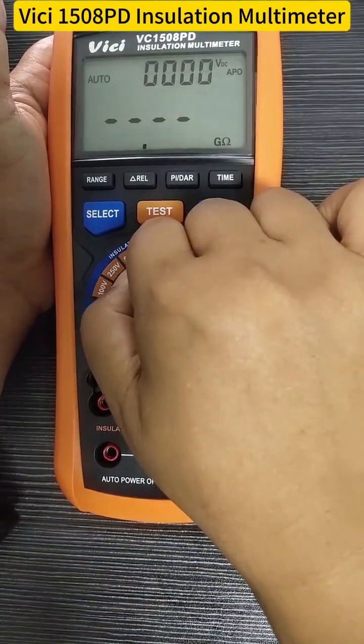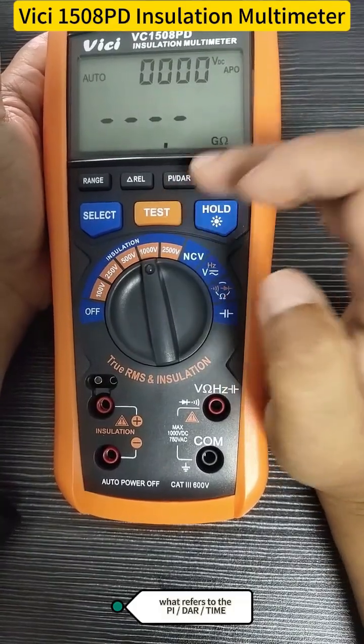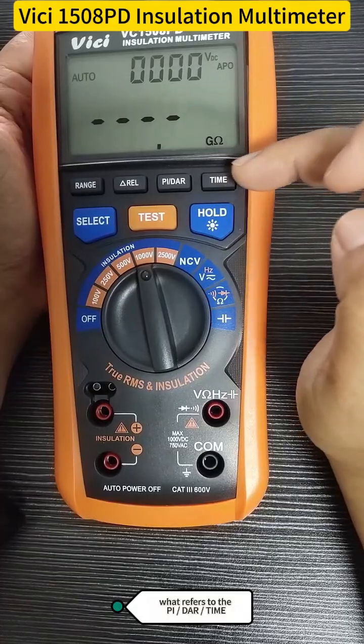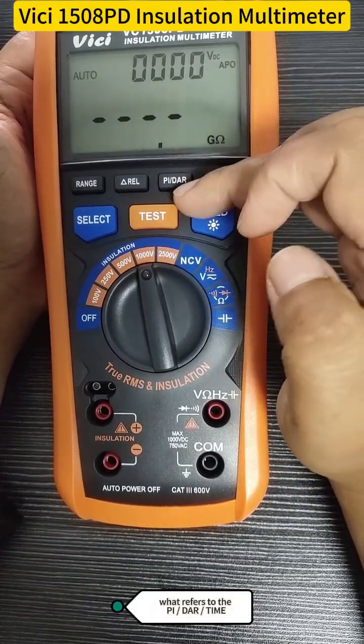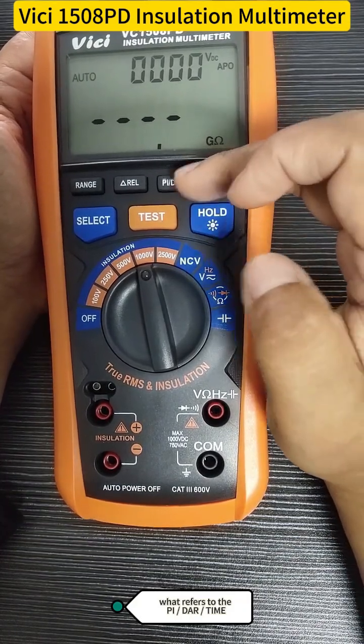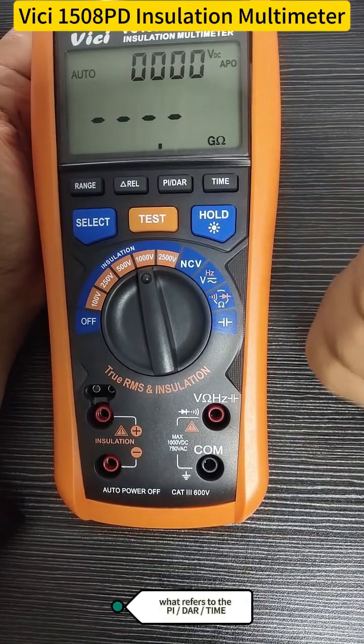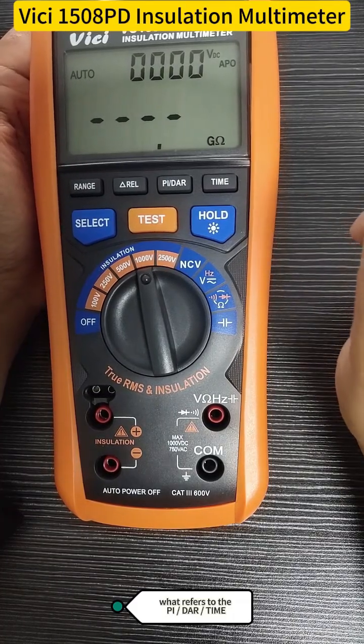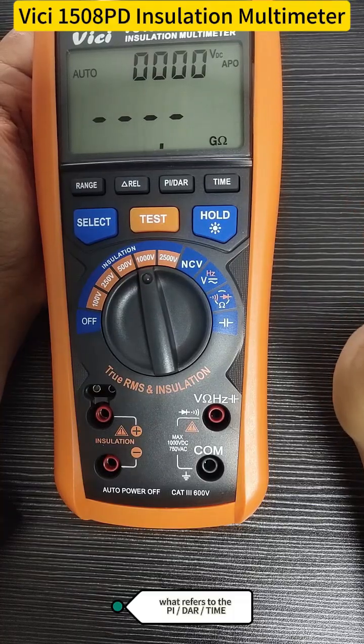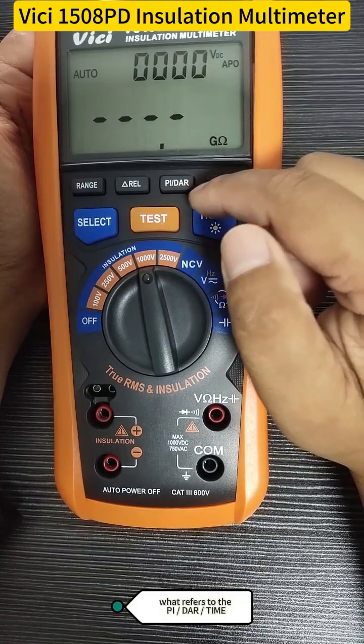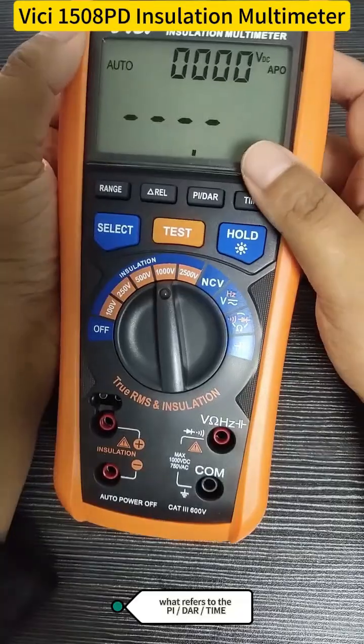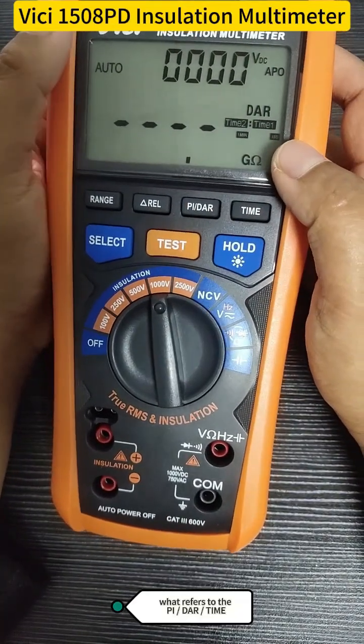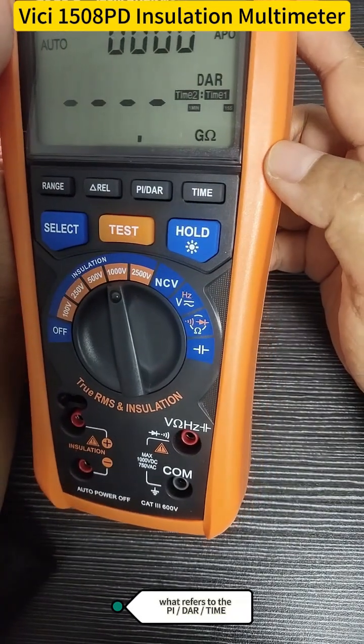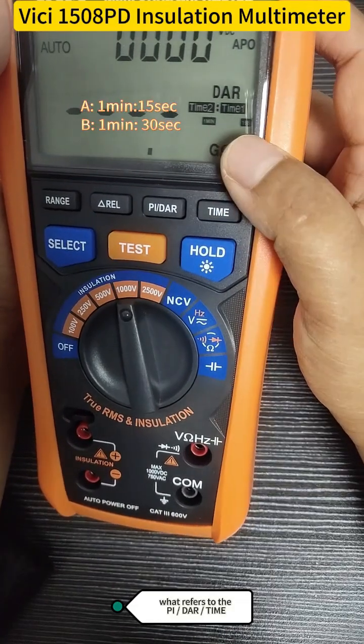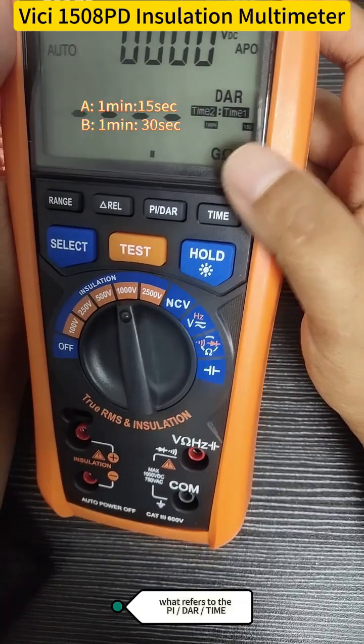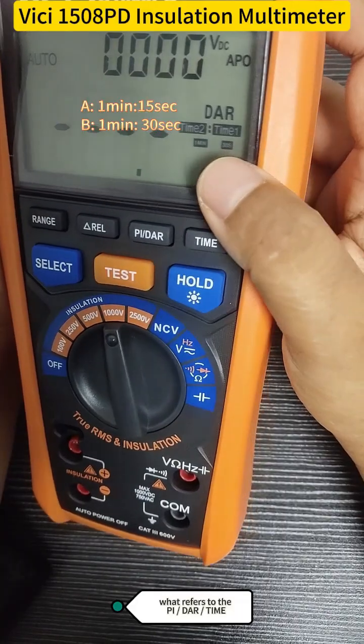Okay, now let's see the insulation understanding points. When we check the insulation, this tester gives the PI, that means polarization index, and DAR, dielectric absorption ratio. It can calculate them automatically, perfect for finding hidden issues like moisture, dust build-up, and degraded insulation. We can press this PI-DAR button to switch between them. Now, okay, let's start with the DAR, dielectric absorption ratio. It is the insulation resistance measured at 1 minute divided by the insulation resistance measured at 15 seconds, or it may be 1 minute to 30 seconds.